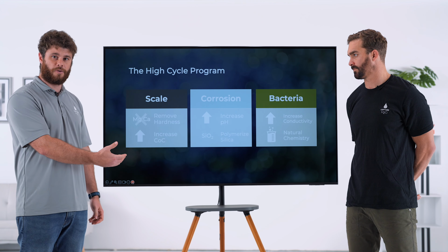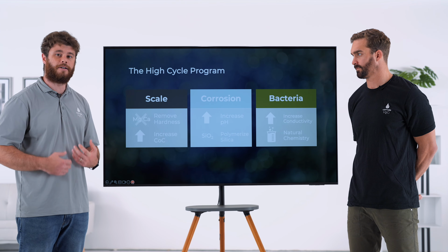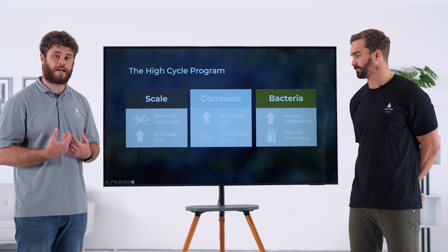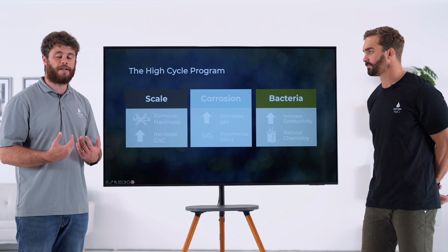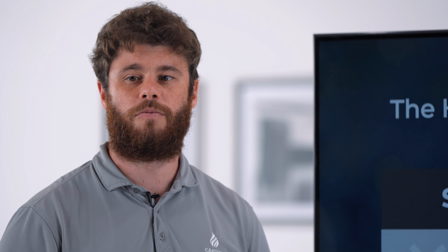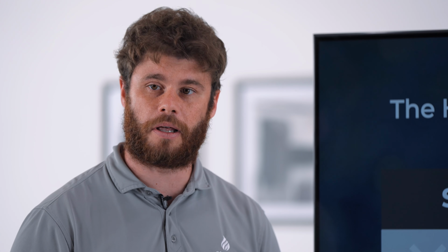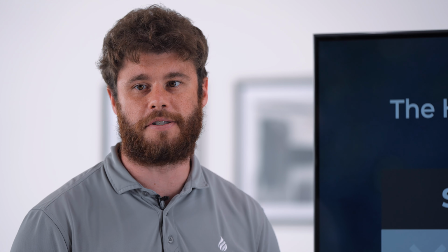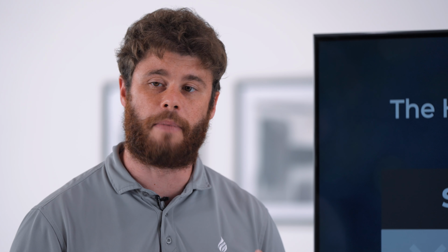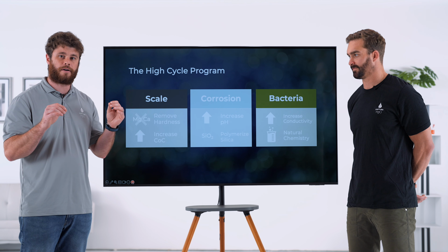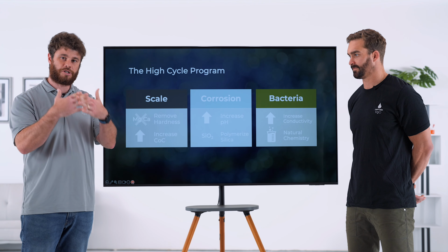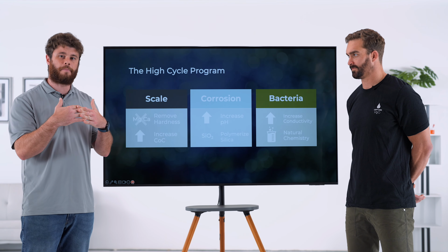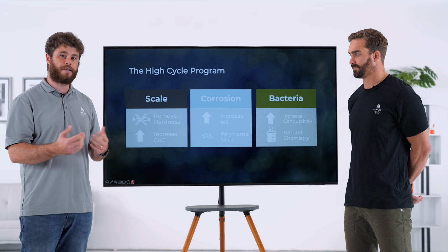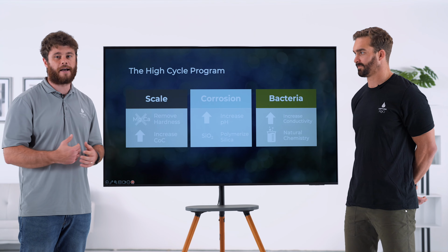Which leads us to step two, corrosion control. When we begin increasing our mineral concentration and our cycles in the cooling tower water, our pH will also rise naturally. When we reach a pH above 9 and our silica, which is one of the many dissolved solids in water, reaches a concentration above 200 parts per million, that will cause the silica ions to convert from monomers, these free-floating ions in the water, to a polymer, merging together and creating a single ion-thick passivation layer coating all the wetted surfaces in the system, acting as a natural corrosion inhibitor.